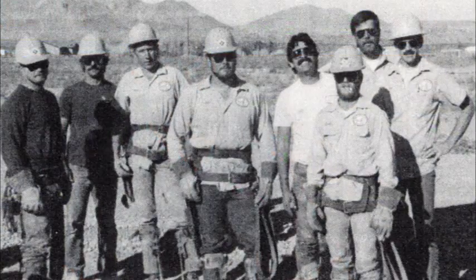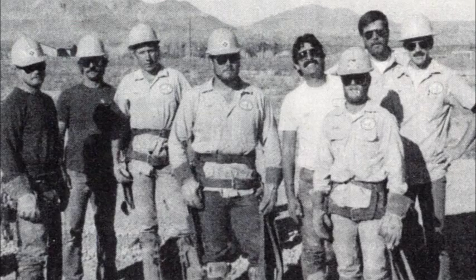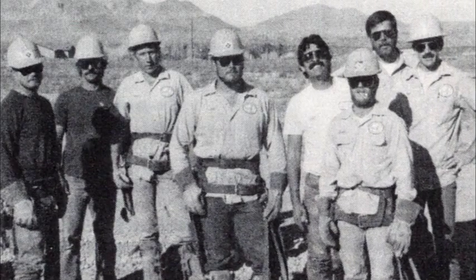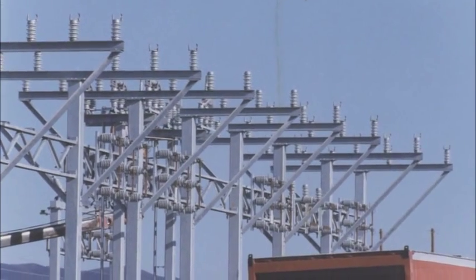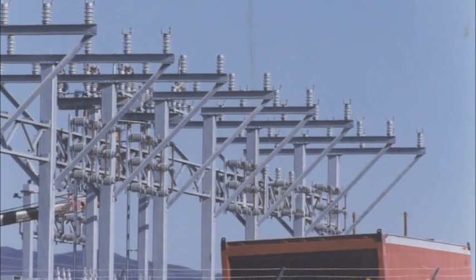In the early days, we didn't have much technology. The breakers that we had would operate on a fault, but we had no indication that they did or didn't operate except by customer phone calls. So when a customer would call, we would go to that customer's locale and work our way back toward the substation.